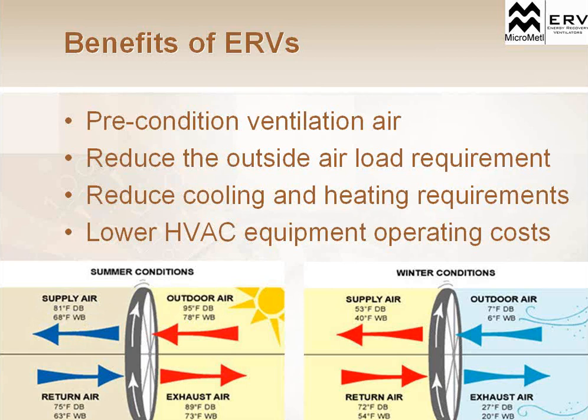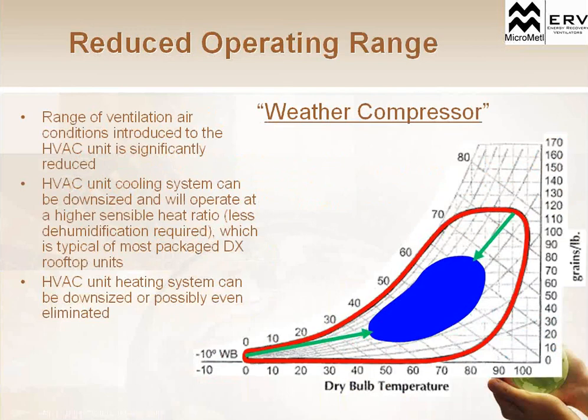So we're reducing the amount of cooling capacity we need out of that rooftop because we don't have to configure it to overcome some of those outdoor air ambient conditions. Essentially that's going to lower the HVAC equipment operating cost, because we're not relying on that quote-unquote rooftop or air handler or other main component to heat and cool that outside air. We're using the energy recovery unit to pre-treat the air before the rooftop unit even sees it. So we'll go a little bit further into that to make it a little more clear.